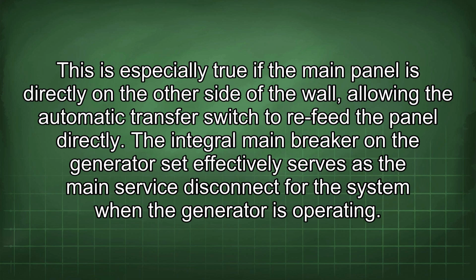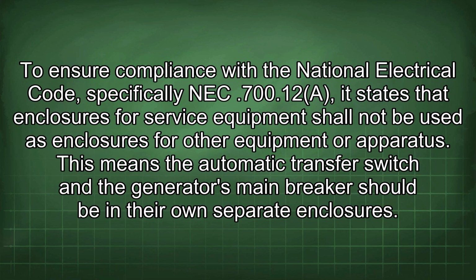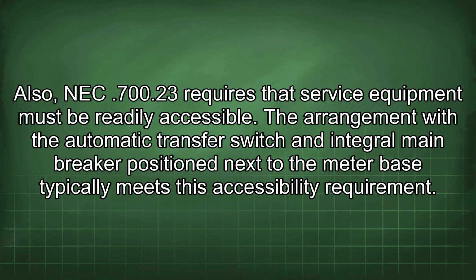The integral main breaker in the generator set effectively serves as the main service disconnect for the system when the generator is operating. To ensure compliance with the National Electrical Code, specifically NEC 700.12(A), it states that enclosures for service equipment shall not be used as enclosures for other equipment or apparatus. This means the automatic transfer switch and the generator's main breaker should be in their own separate enclosures. Also, NEC 700.23 requires that service equipment must be readily accessible.